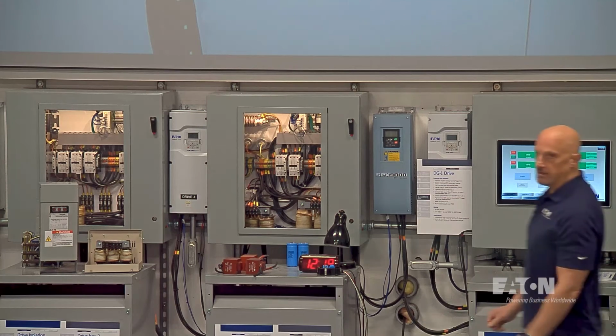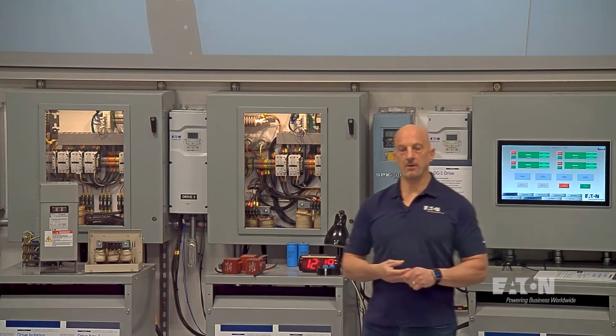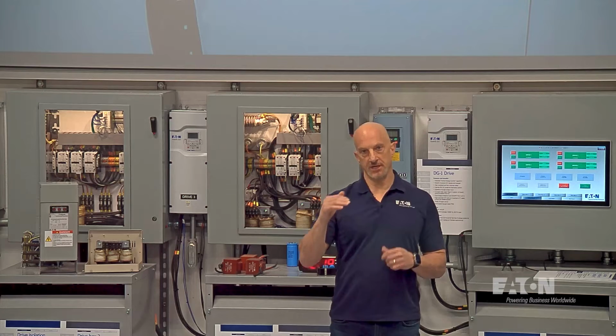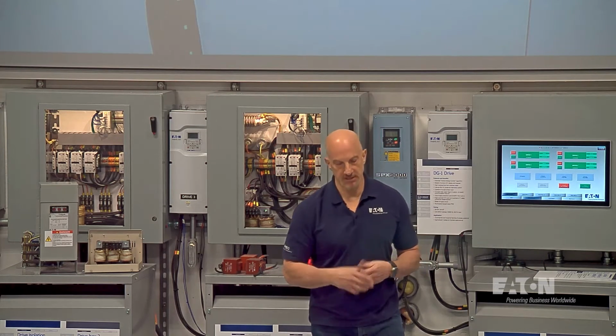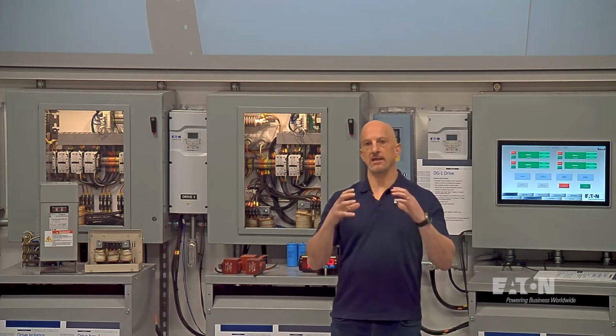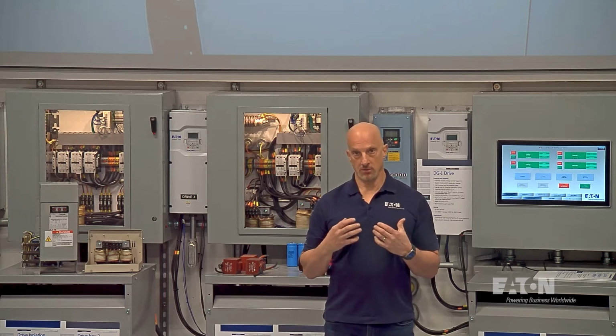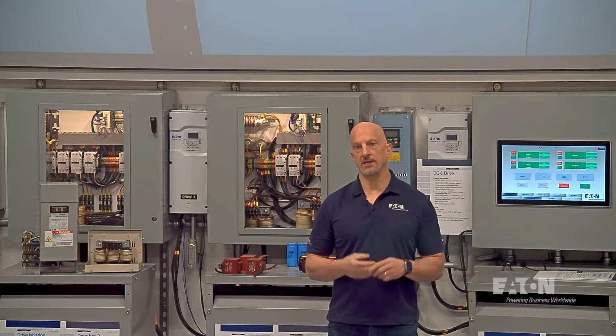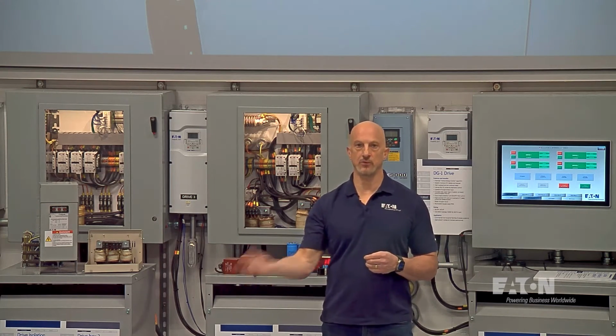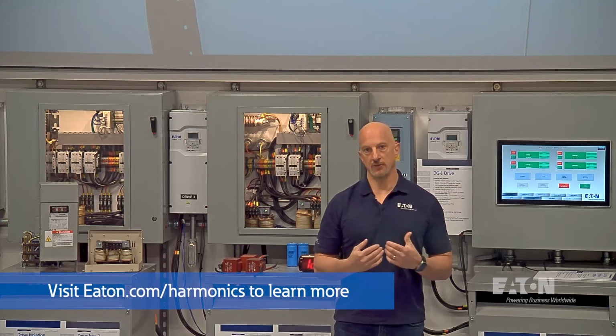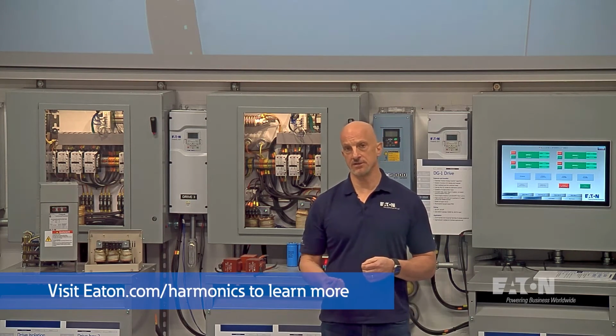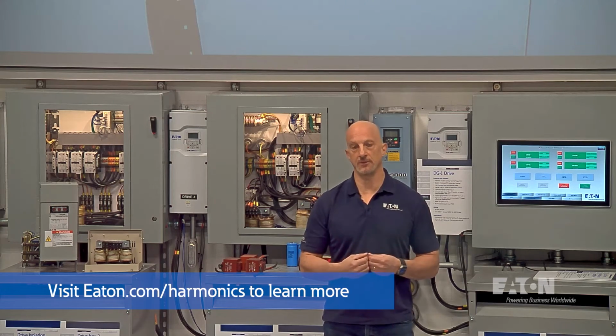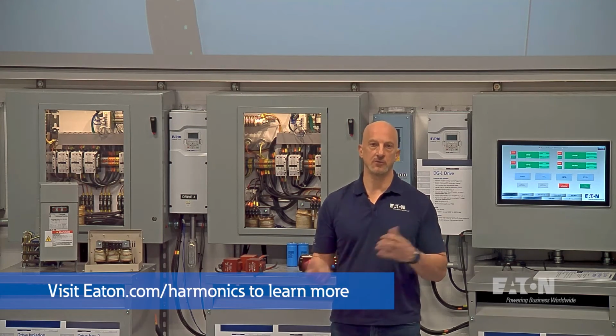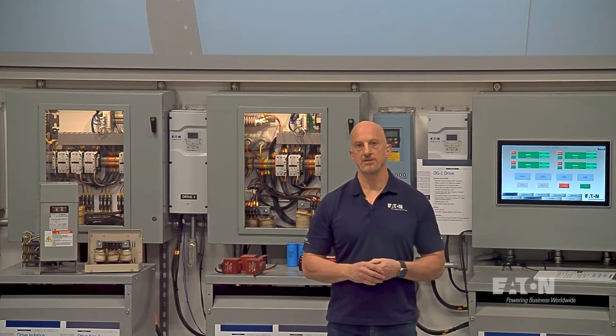So in at least one other video, we talk a little bit about voltage distortion causing current distortion. But we can get that kind of harmonic influence from the utility. But again, that's because your neighbors are screwing up the power system enough for you to get voltage distortion. But as far as current distortion goes, that comes from us, comes from the loads, and we infect ourselves. So we have to control the flow of that current to control harmonics.